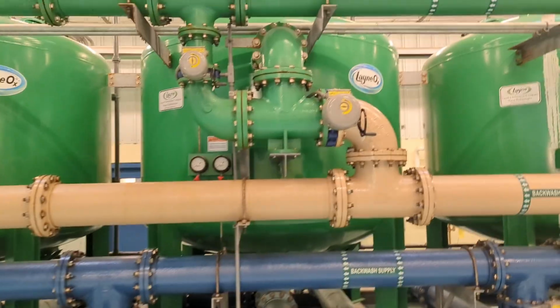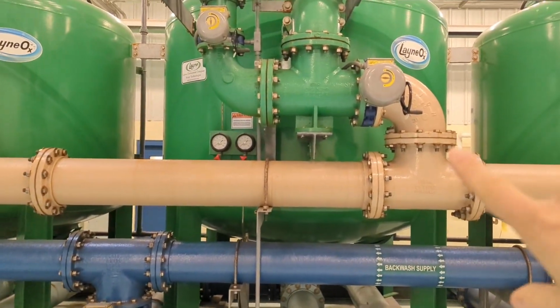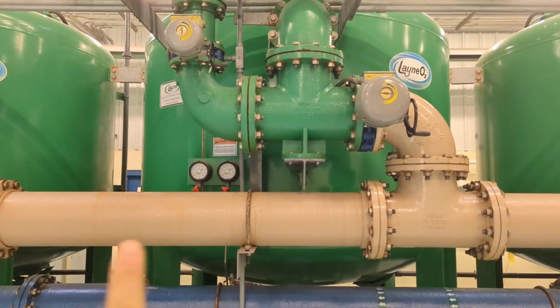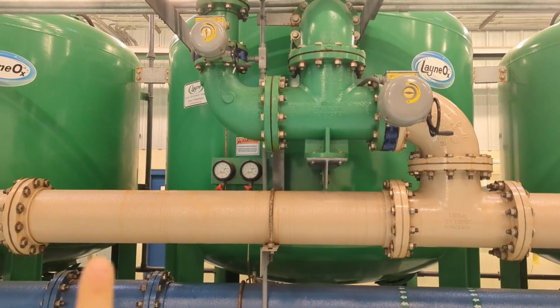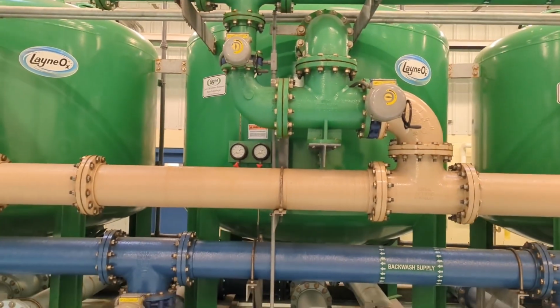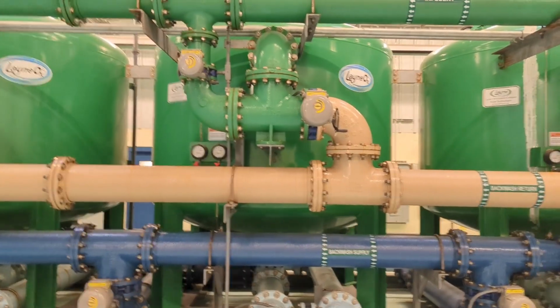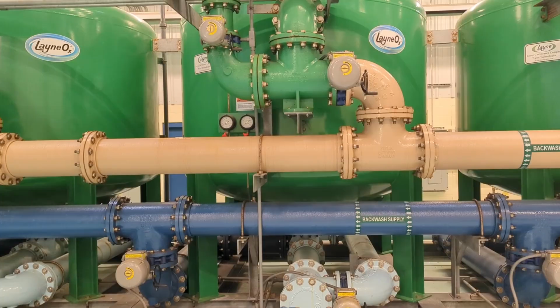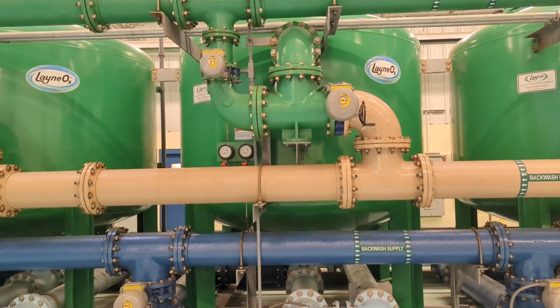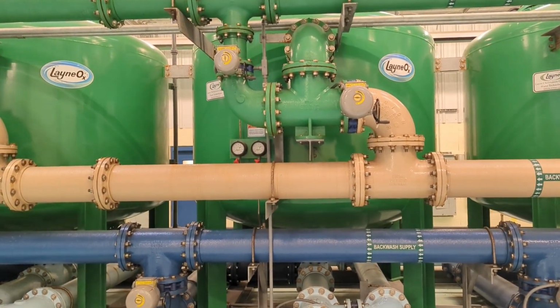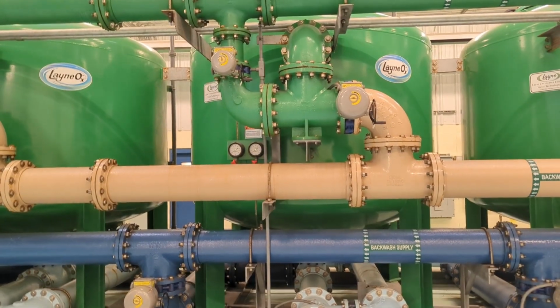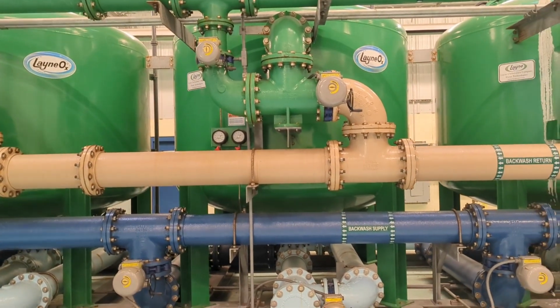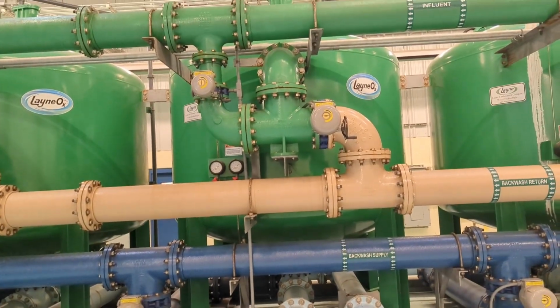We backwash once a day. So the tan line, this line right here, is the backwash line. You wash these filters once a day, and what does that washing do? Cleans the material out, much like a swimming pool. Anybody that has a swimming pool has a sand filter and you backwash to remove all the iron and manganese. These are just large swimming pool filters, right?